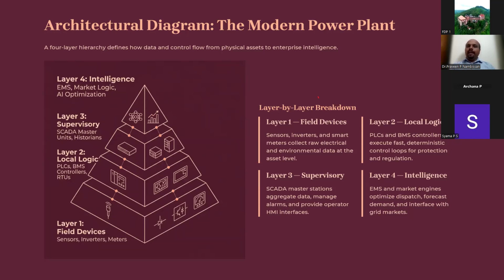Next is layer 2, which is local logic, having PLCs, BMS controllers, and remote terminal units. In an industry, sensors normally go to field termination devices, then to junction boxes. From the junction box, through cables, it goes to the central control room marshalling cabinet, and from there directly to the PLC. The PLC is connected to the HMI, which is the SCADA.